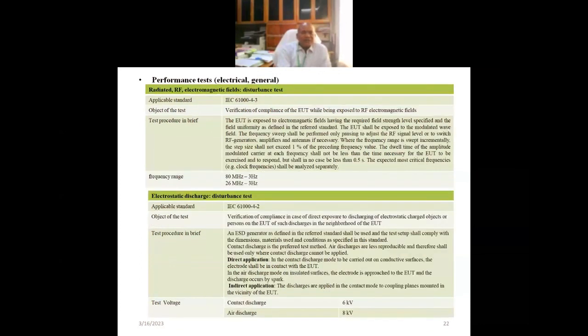Performance test, that is electrical in general: the radiated RF electromagnetic field disturbance test, and the applicable standard is IEC 61000-4-3. The object of the test is verification of compliance of the EUT while being exposed to RF electromagnetic fields. The test procedure: the EUT is exposed to an electromagnetic field having the required field strength level specified, and the field uniformity is defined in the referred standard.